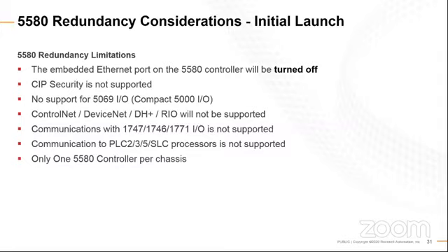In our documentation for a process-based system, we would say just one controller per chassis, but from a technical point of view, we did have the ability of supporting up to two controllers per chassis in an L7 style redundant platform. Going forward with an L8 style design, we will only be supporting one 5580.